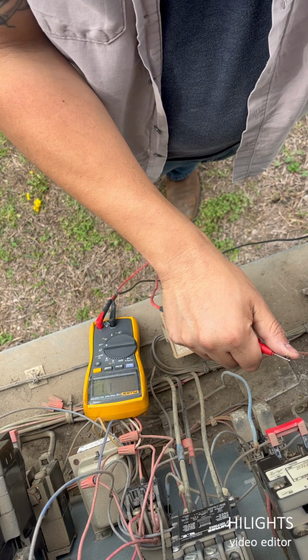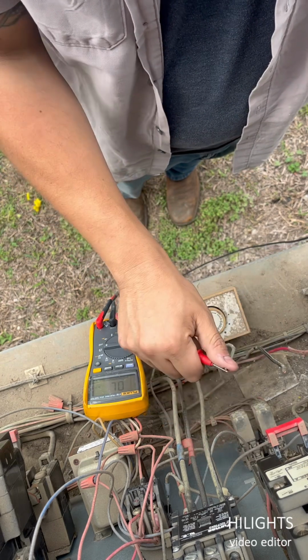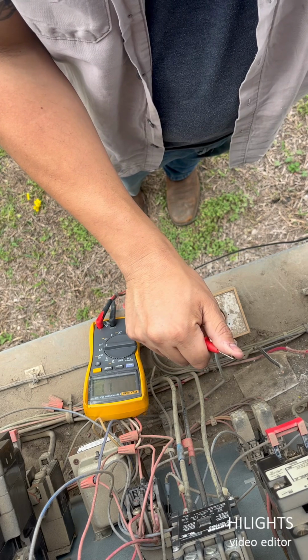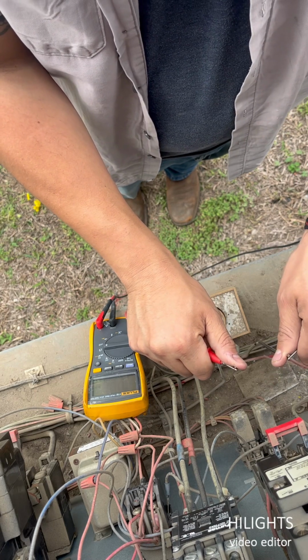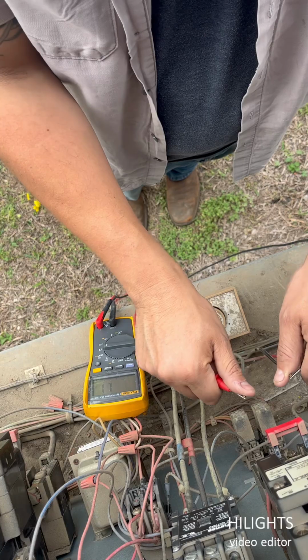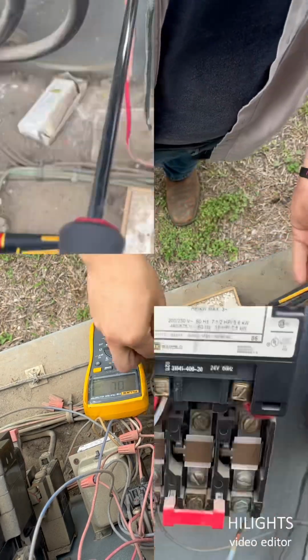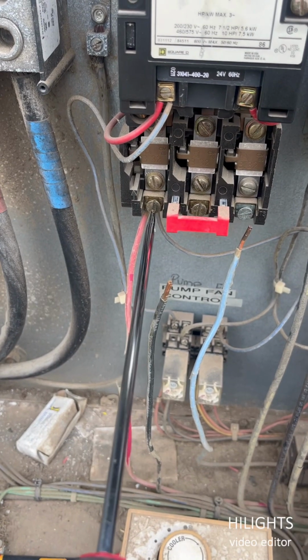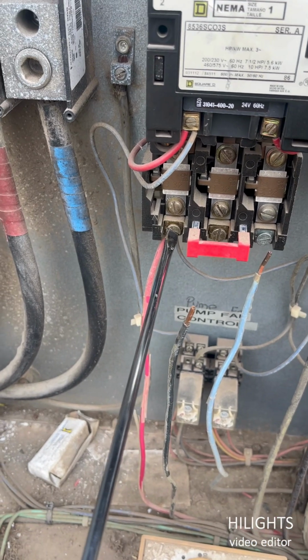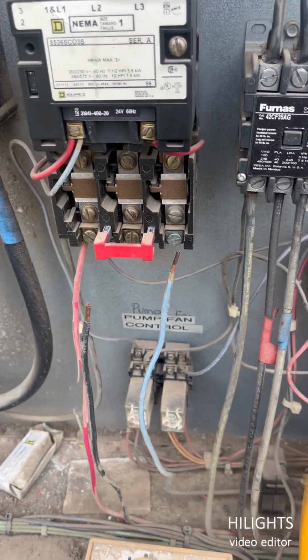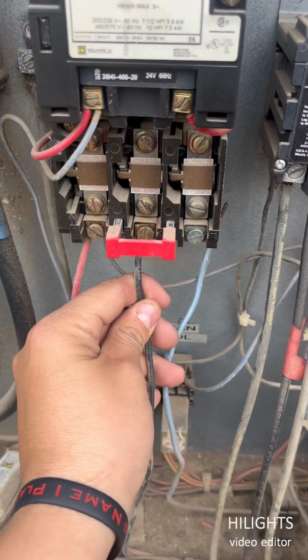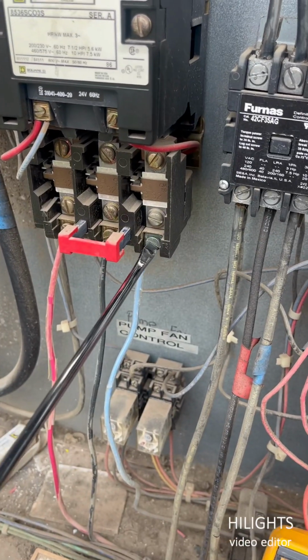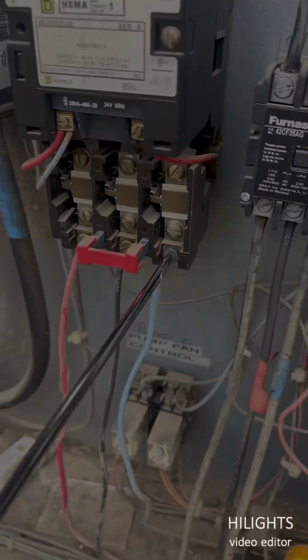So here I'm testing between the legs of the pump, checking ohms. Now it's a 3-phase motor, so they should all read the same between all the legs, which they did. Alright, let's put these wires back on. The pump is good. Make sure they're tightened down, remember.